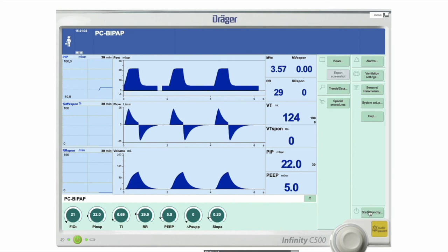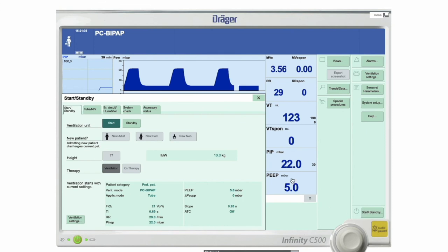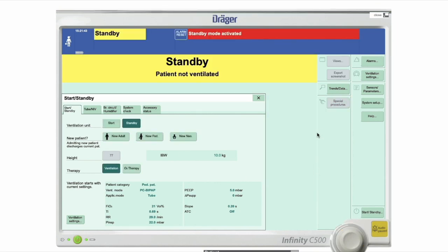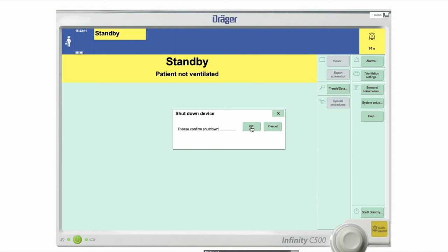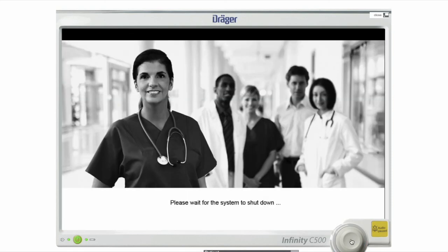If you want to turn it off, because the patient's either got better or been extubated, you press the start standby button again. You click on standby, accept. It will then alarm. So then you can stop it making noise while you then reset the alarm and confirm, and that will be the ventilator now back in standby. To switch it off, you switch it off here. You're never required to switch it off because, well, it depends on the situation, but you wouldn't be required to switch it off. But if you did, you'd press it, it would ask you to confirm. You say okay, you then need to reconfirm. You get that wonderful splash screen you saw in the beginning, this time in black and white. And then it should switch itself off.